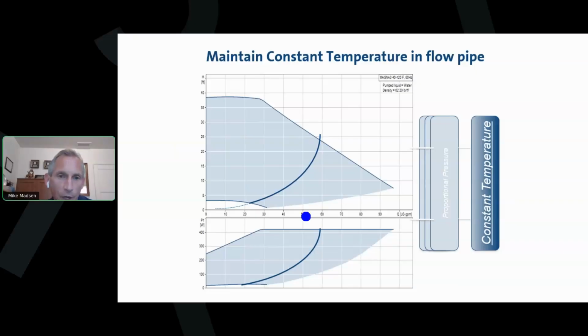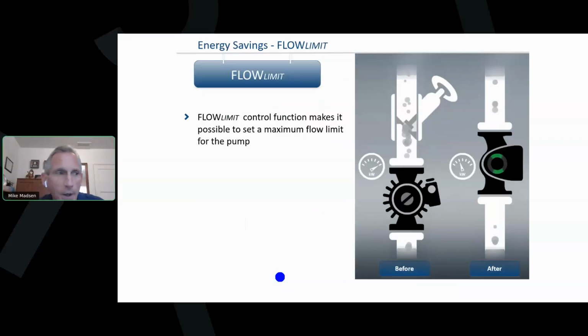If the flow requirement's only 50, you can see how much our head dropped and how much our power dropped. So unlike a control valve that just continues to waste energy, when we slow these pumps down on the VFD, we're going to come down this power curve here, and we spend a lot of time operating down here. We're using very little power at these lower flow rates.